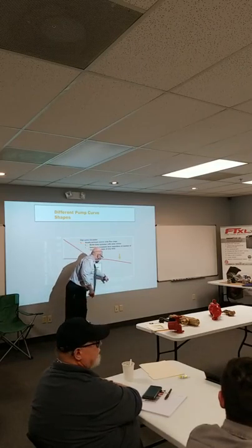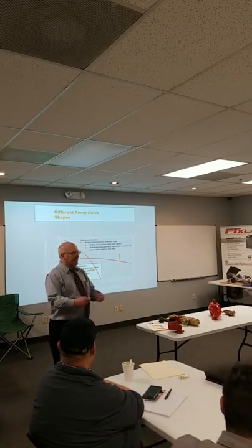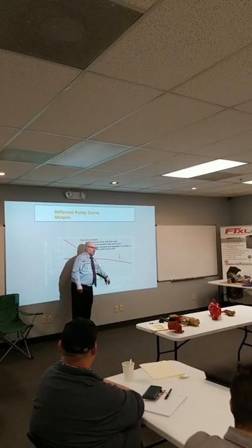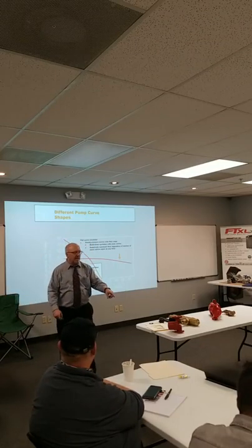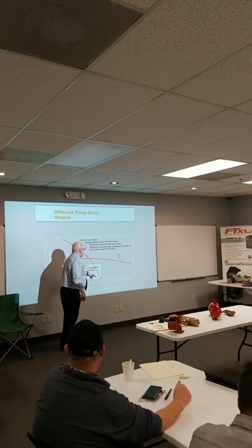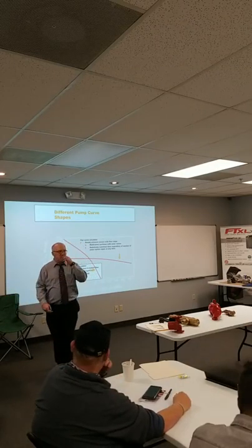What if I have a 120,000 BTU boiler, and remember our equation was divided by 10,000? I need 12 gallons a minute for that system. The old pump did 12 gallons a minute. I put the new pump in because it's cheaper, it's smaller, it's quieter, and it fits the same face-to-face dimension. Are you getting the same amount of heat out of it? No, because it only goes to 10. It only goes to 100,000 BTUs. But you're picking up the motor.